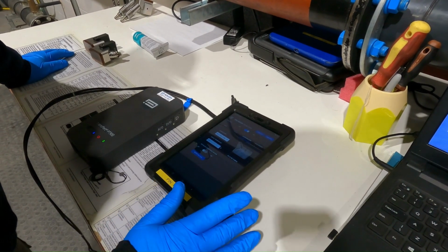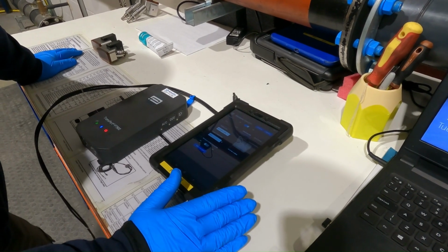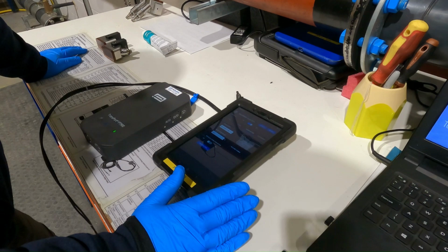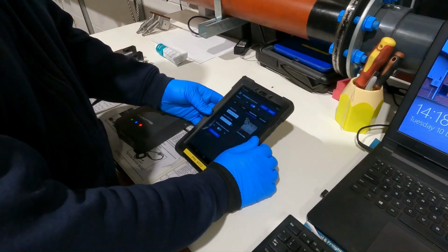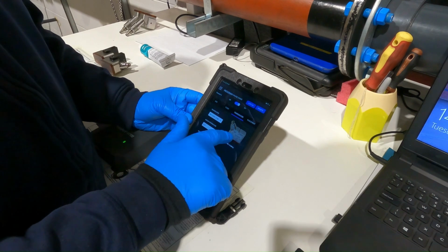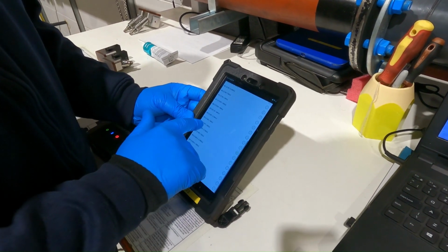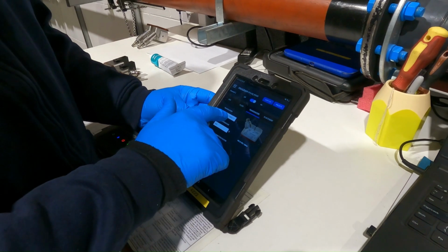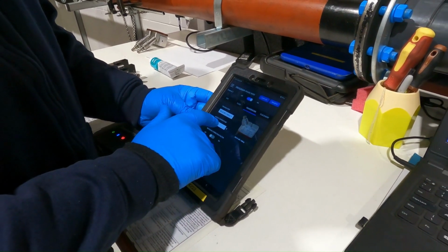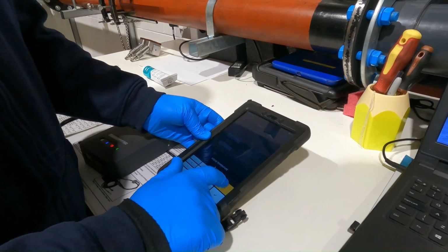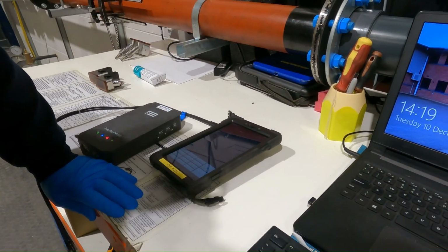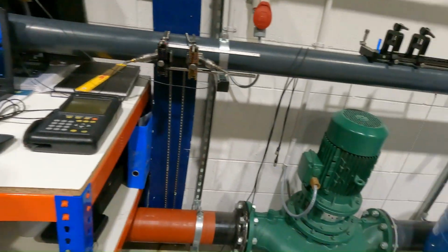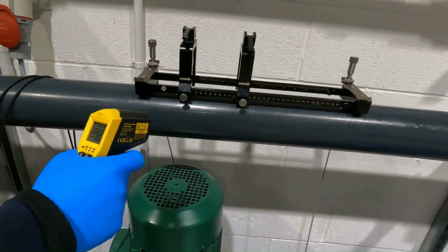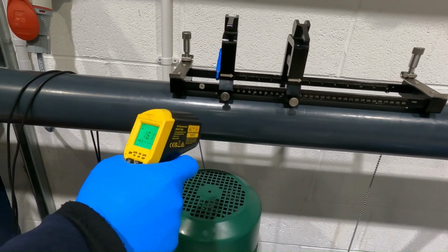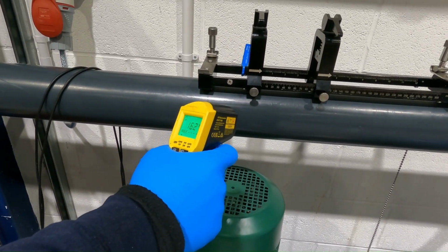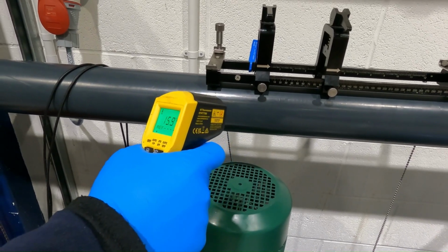Transducer. The transducer depends on the pipe and the application. On this 4-inch pipe we're going to be using 592s. To select your transducer, you get a nice little picture as well now. Find 592s, select it. There we go, 1 megahertz 592. Wedge temperature. This is the surface temperature of the pipe where the transducers are going. Just take an average. Yeah, I'll go for 16 on that.